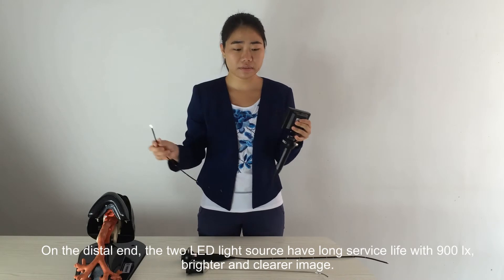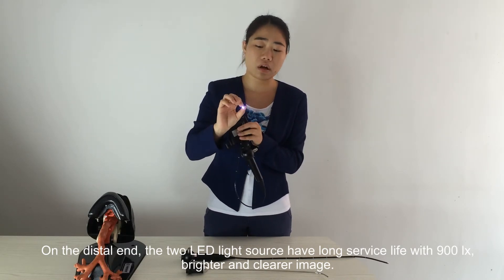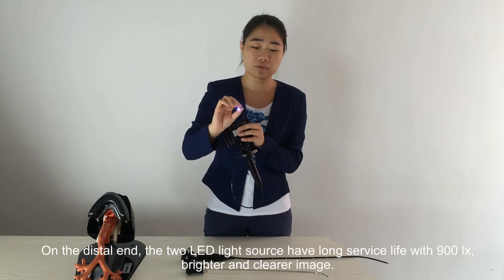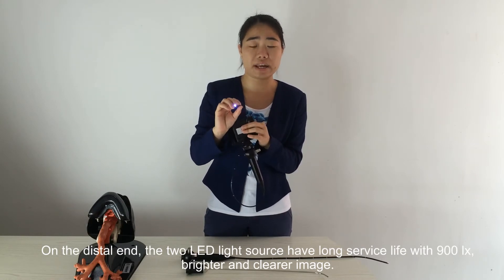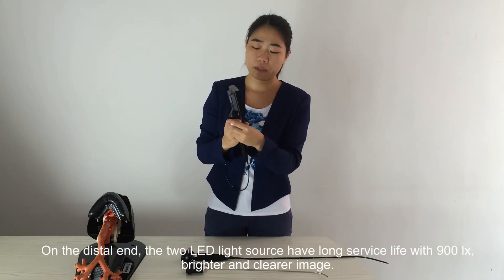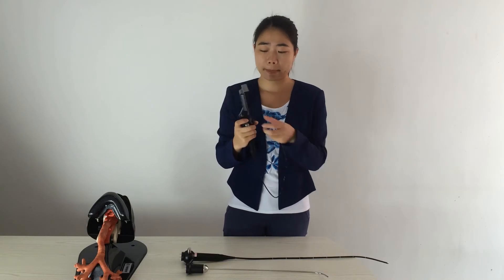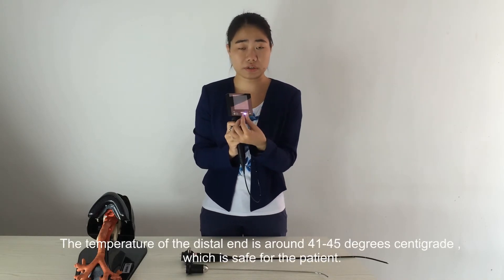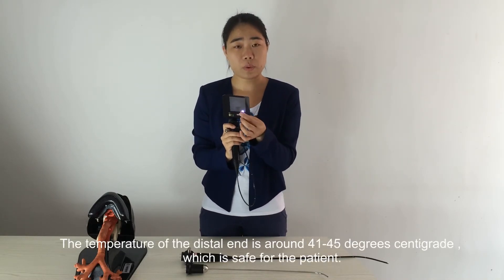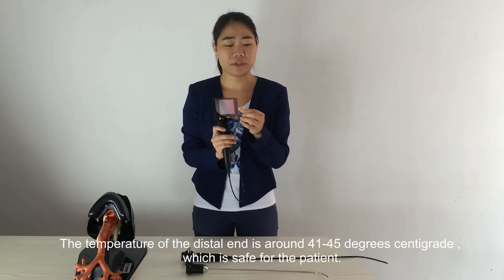On the distal end, the 2 LED light sources have a long service life with 900 lux, enabling a brighter and clearer image. The temperature of the distal end is around 41 to 45 degrees Celsius, which is safe for the patient.